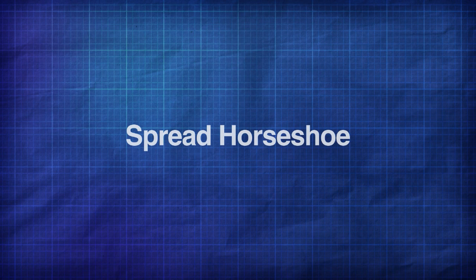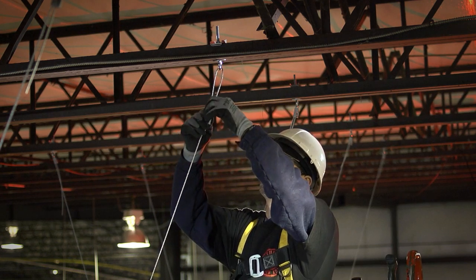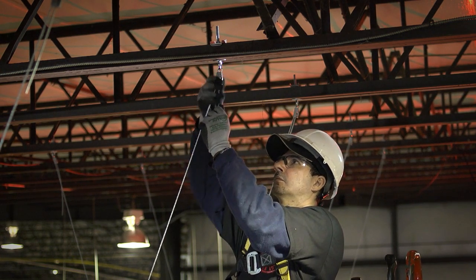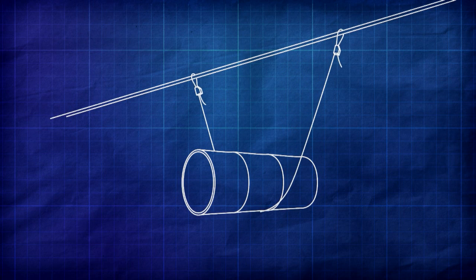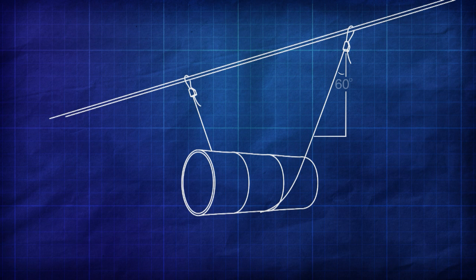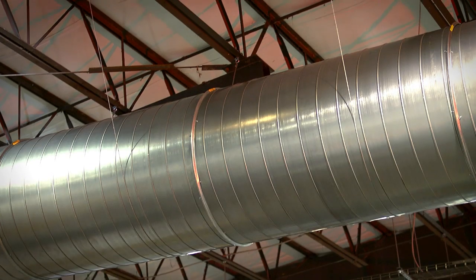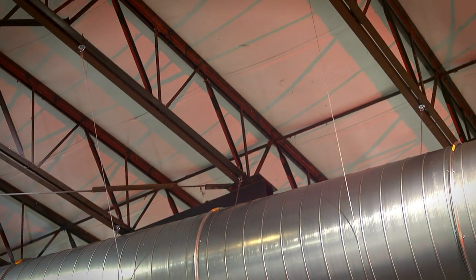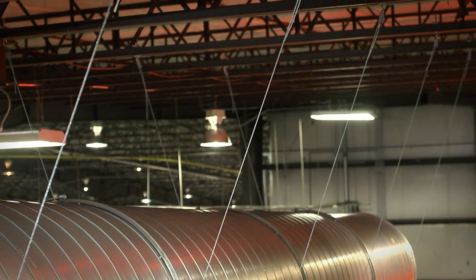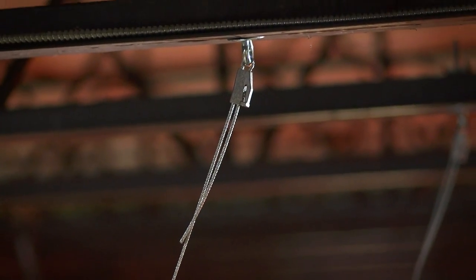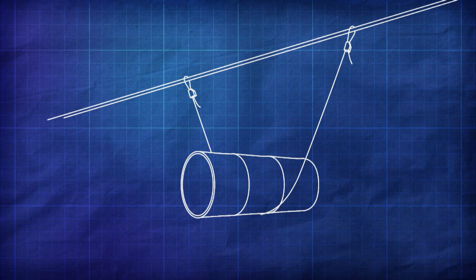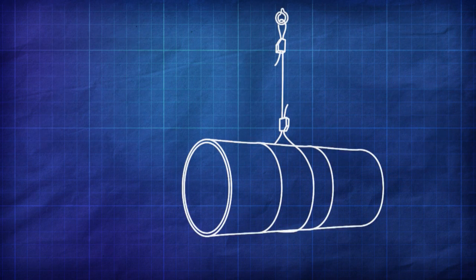The third configuration is the spread horseshoe. Similar to the standard horseshoe, the spread horseshoe method can be used for additional stability. By spreading the points of contact of the steel cables to the side, the spread horseshoe creates a measure of cross-bracing. When supporting ductwork using the spread horseshoe configuration, increasing the angle of the wire from vertical increases the stress on the Ductmate clutcher system and reduces its working load limit. The system should never be used in a configuration which exceeds 60 degrees from vertical. However, since there are 2 steel cables, the total working load limit of this configuration is no less than the load limit of a single steel cable using a standard loop configuration.